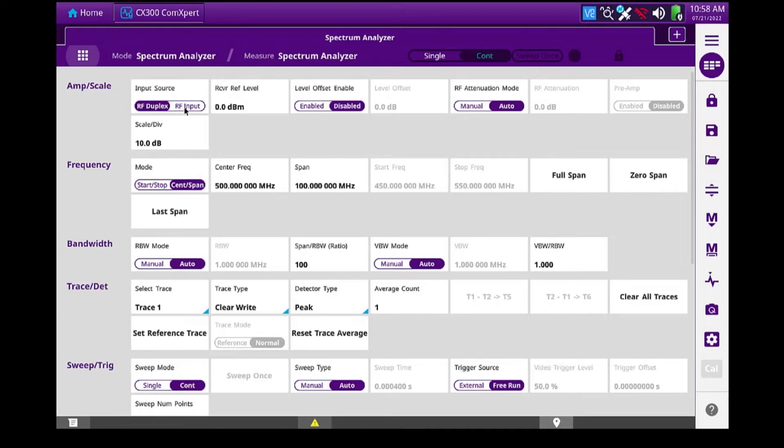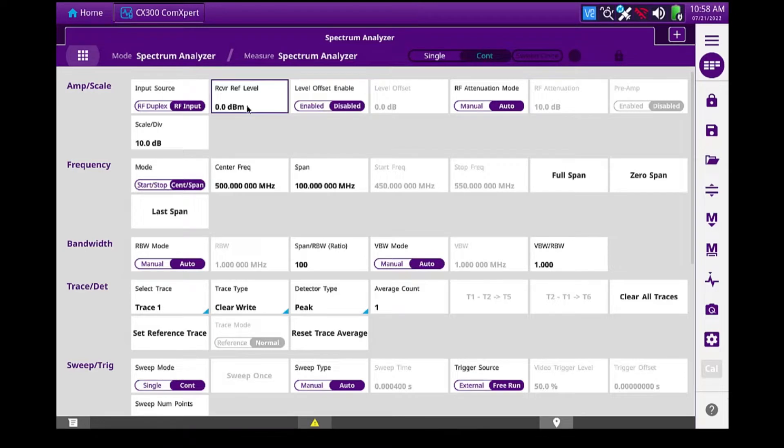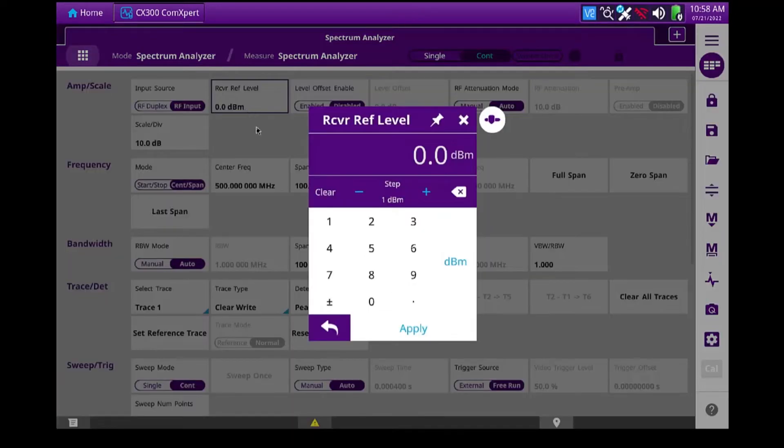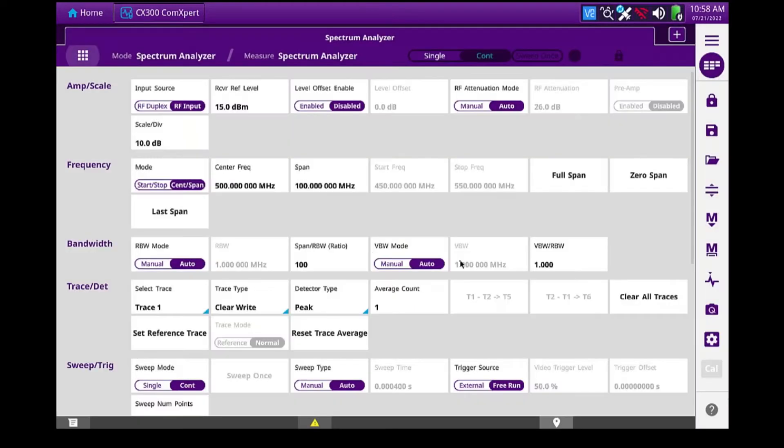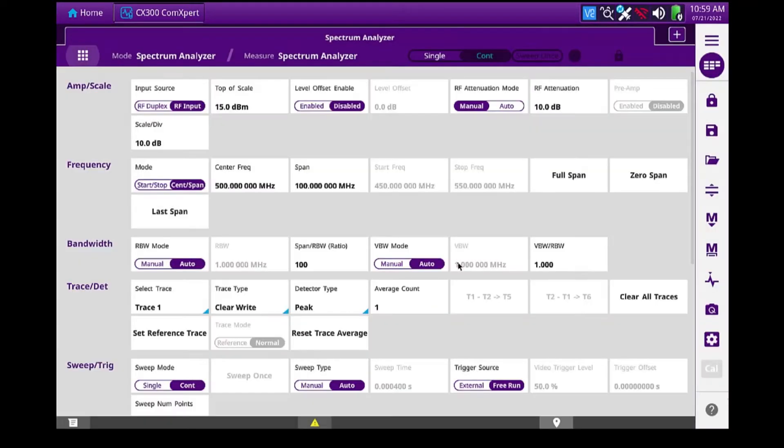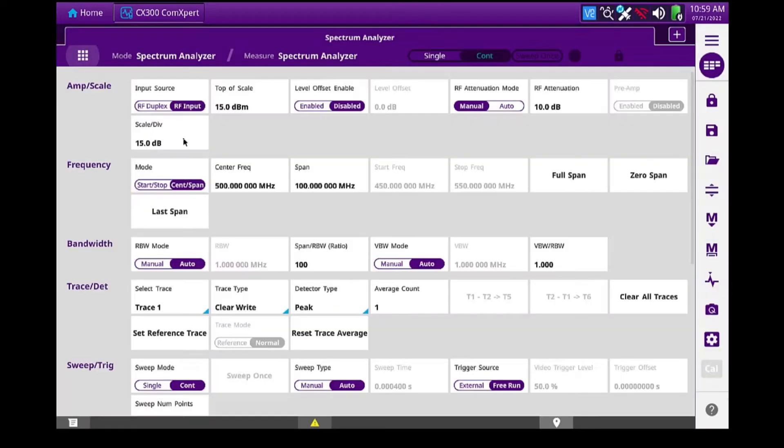So I'm going to use my RF input port. It's the higher sensitivity port. I want to set my top of scale reference line to plus 15 dBm. I want to set my attenuation to manual mode, and I'm going to give it 10 dB of input attenuation. And I'm going to change my scale per division to 15 dB per division.